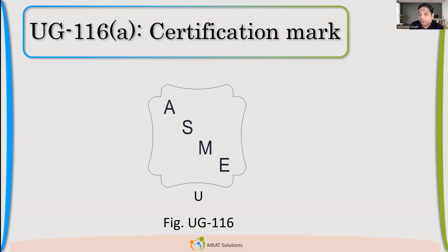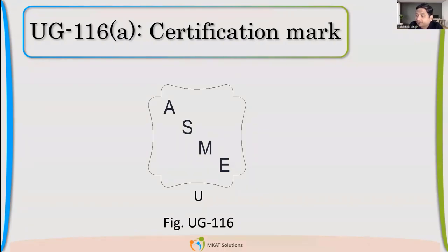When we stamp a vessel, your organization is authorized to use this mark. The main thing is that you are following the inspection requirements in the code. If you refer UG-90 through UG-97, there are inspection requirements for how the vessel should be inspected. If you are using an authorized inspector and meeting all the requirements from UG-90 to UG-97, then your vessel can be stamped.